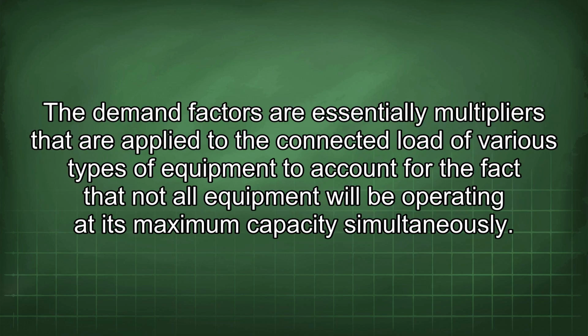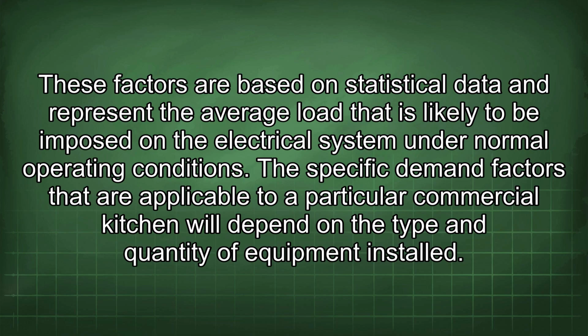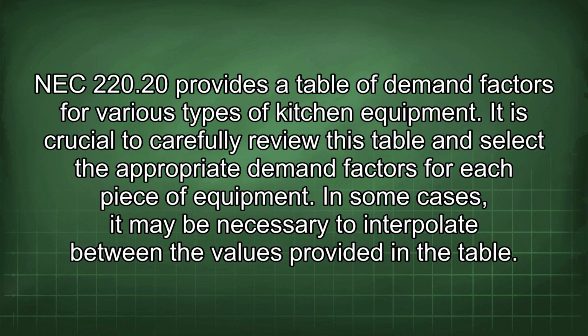The demand factors are essentially multipliers that are applied to the connected load of various types of equipment to account for the fact that not all equipment will be operating at its maximum capacity simultaneously. These factors are based on statistical data and represent the average load that is likely to be imposed on the electrical system under normal operating conditions. The specific demand factors that are applicable to a particular commercial kitchen will depend on the type and quantity of equipment installed. NEC 220.20 provides a table of demand factors for various types of kitchen equipment.